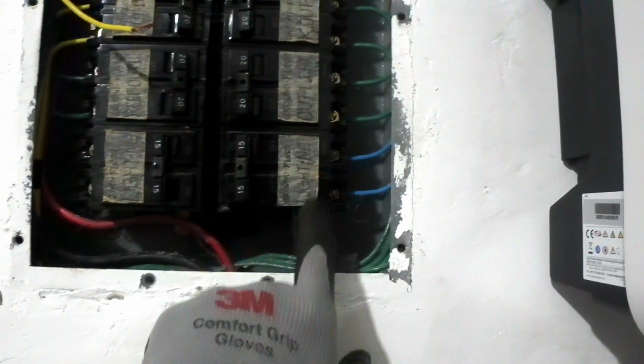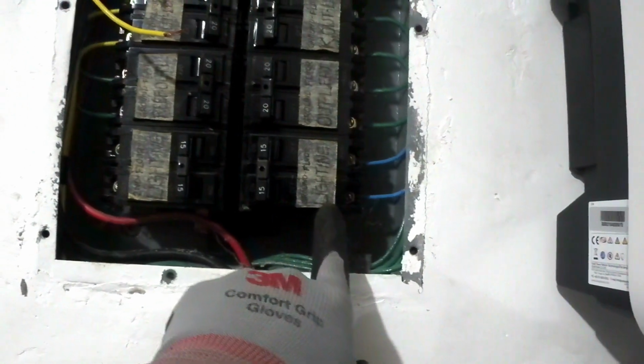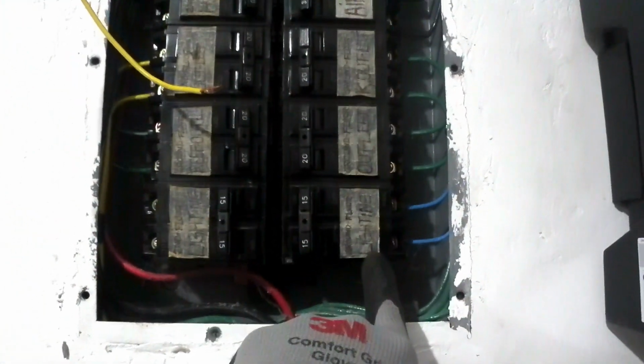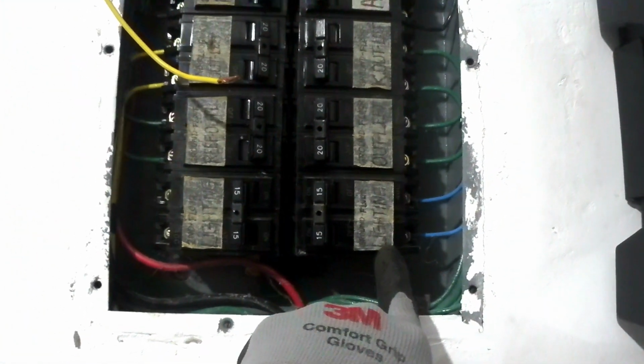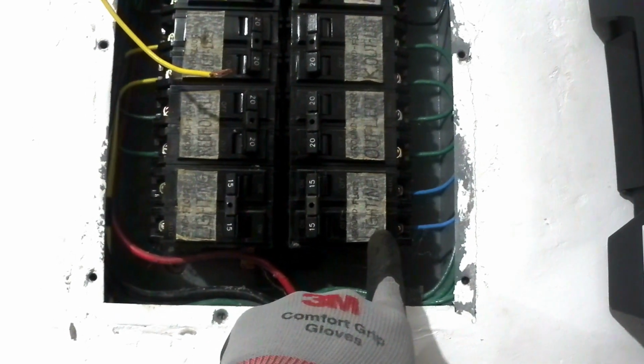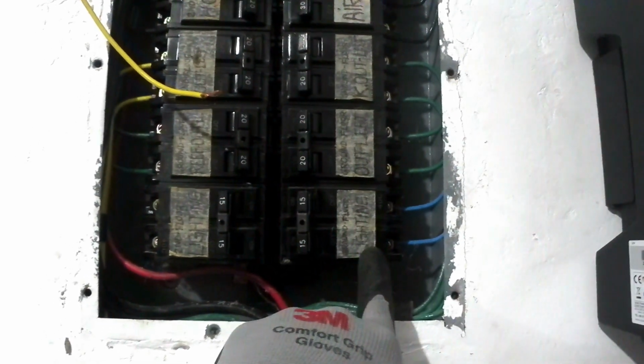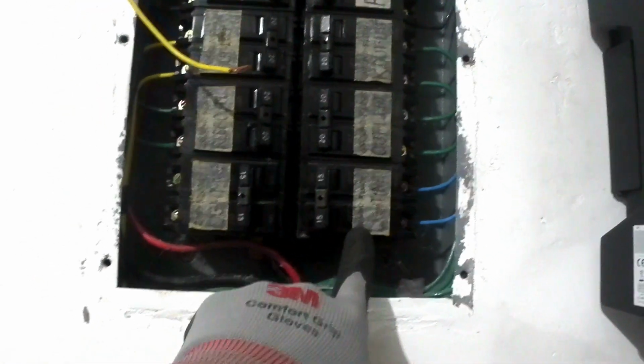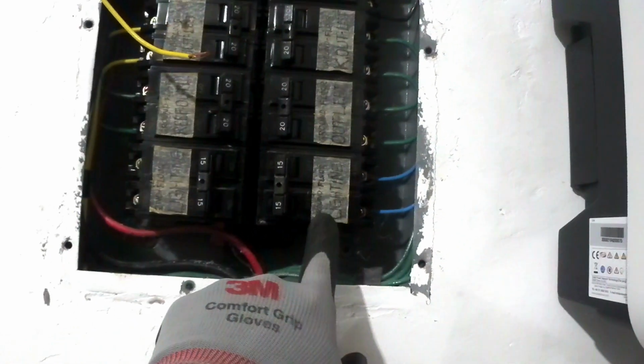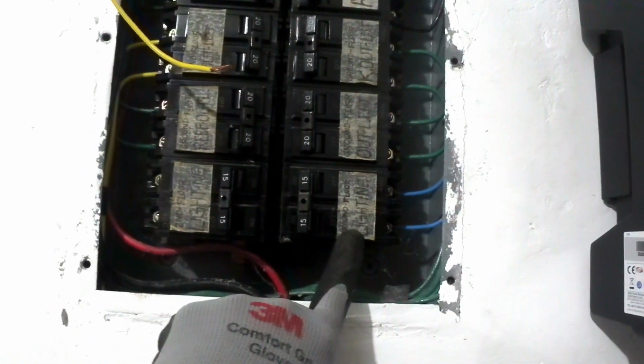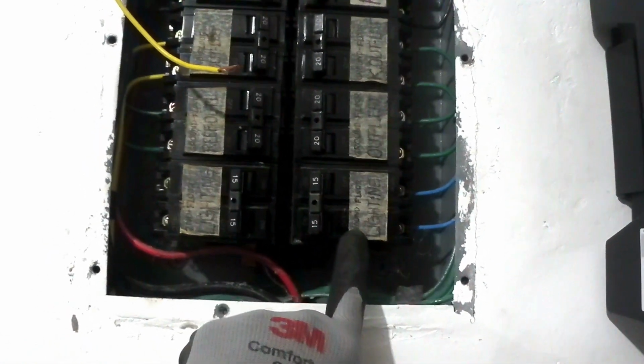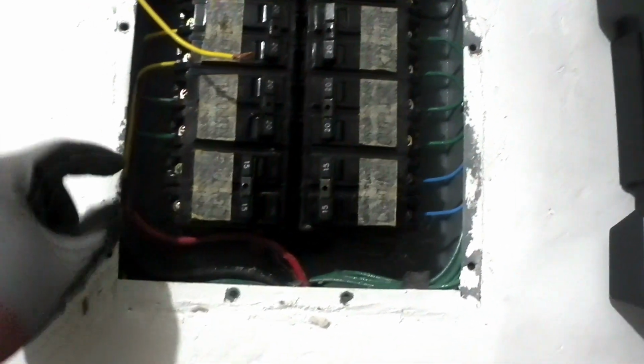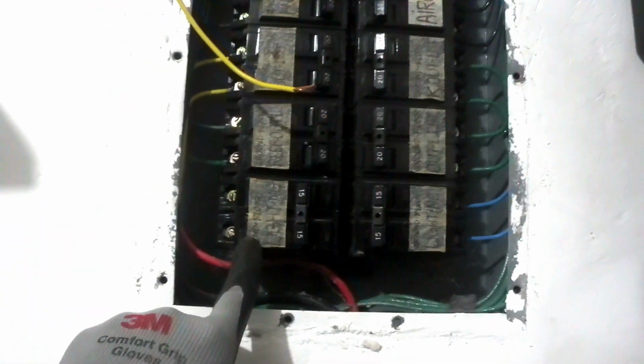Anyway, our load for lights is very minimal, it doesn't even go above 200 watts. From my computation it's around 120 watts, so 15 amperes is more than enough for that purpose. Since this breaker will be freed up, I'll just use it for our inverter. Yep, that's the plan.